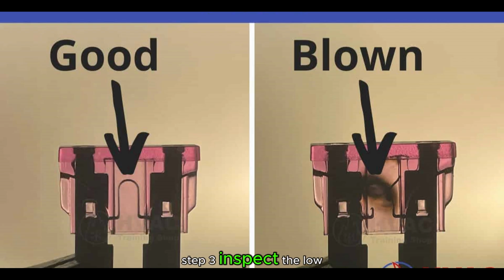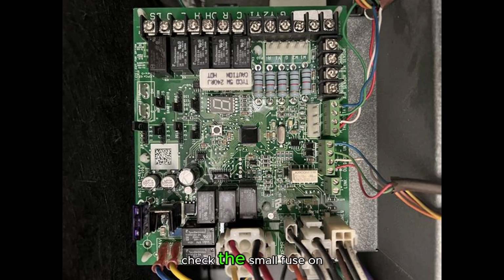Step 3. Inspect the low voltage fuse. If you do have 24 volts at the transformer, but nothing happens at the thermostat, check the small fuse on the board, typically 3 to 5 amps. If the fuse is blown, don't just replace it, find out why it blew.